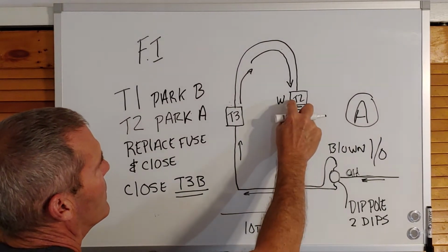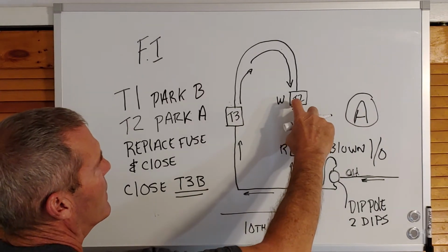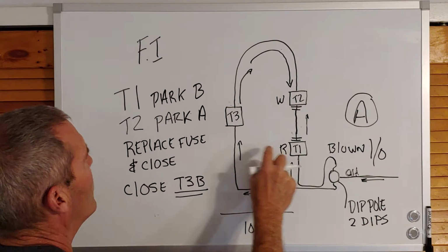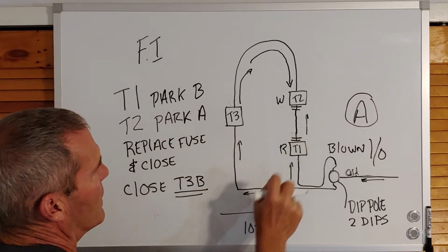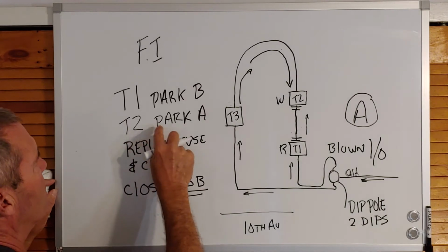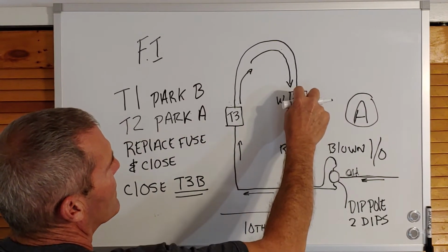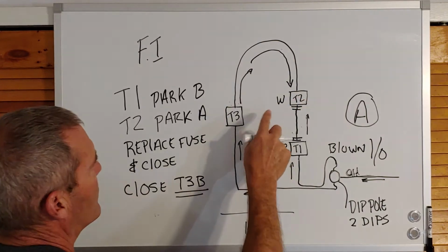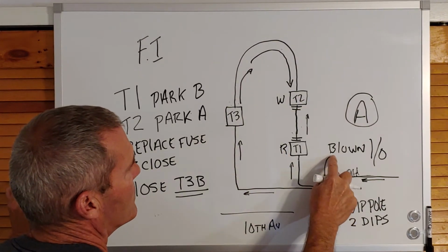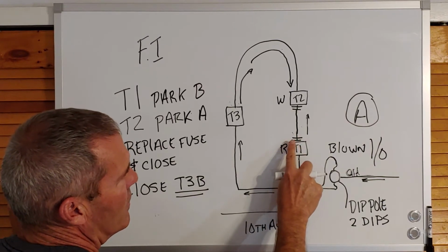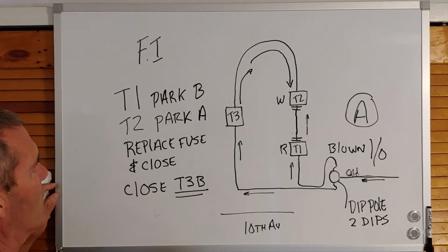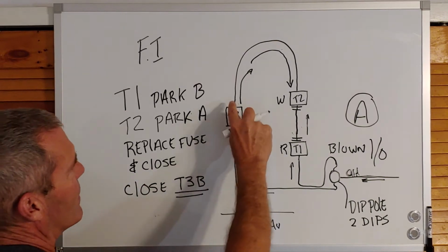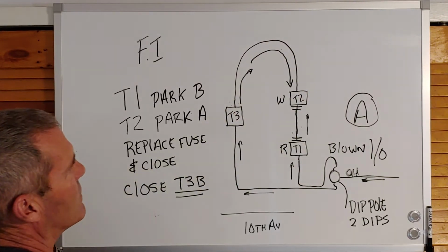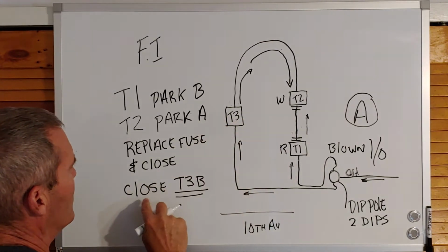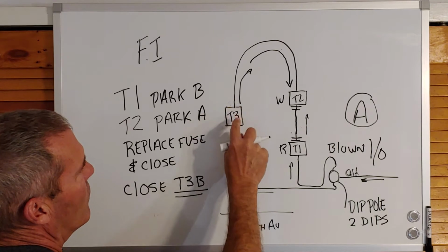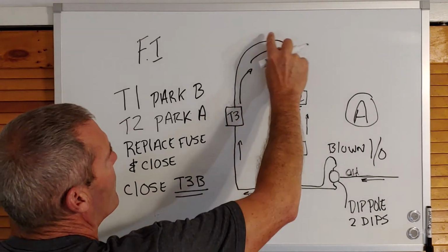That's between T1 and T2, meaning I need to isolate the cable between those two. In T1, I park B, which isolates it from going any further. In T2, I park A, which isolates it from being re-energized from the other direction. I replaced the fuse and have now restored power to T1. It can't go any further because I've parked the elbow going outbound. To get power backwards, or backfeed into T2, I now have to close T3B. It's normally open before, remember those hash marks I had back here, and I'm feeding backwards into T2.